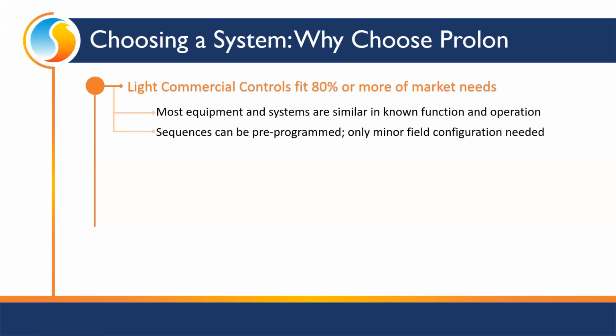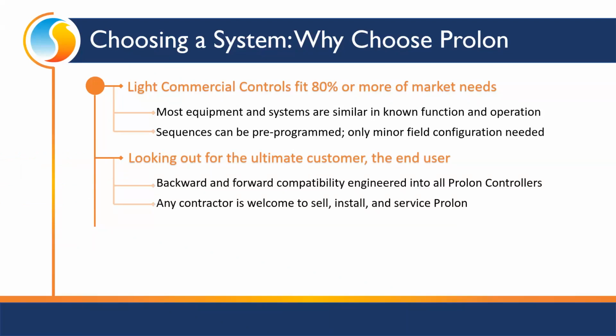So we can pre-program the sequences and just have minor tweaks that are set up out in the field by the installing contractor. Prolon is looking out for the ultimate customer, the guy that's writing the check. So intentionally, for the 23 years we've been in business, we've engineered backward and forward compatibility across all generations of controllers. We have controllers that you can no longer purchase, but if one of those controllers fails, one of our current generation controllers can go in - new can work with old, old can talk to new. Absolute worst case scenario, it's a software update.